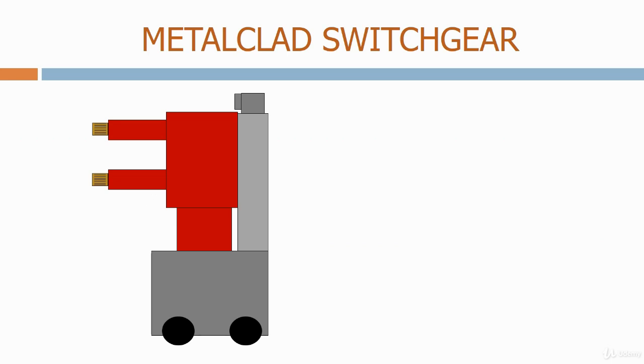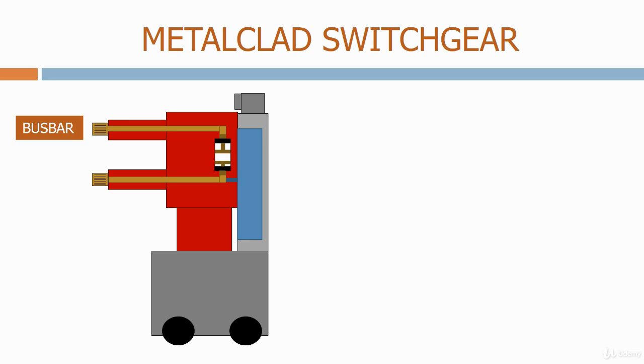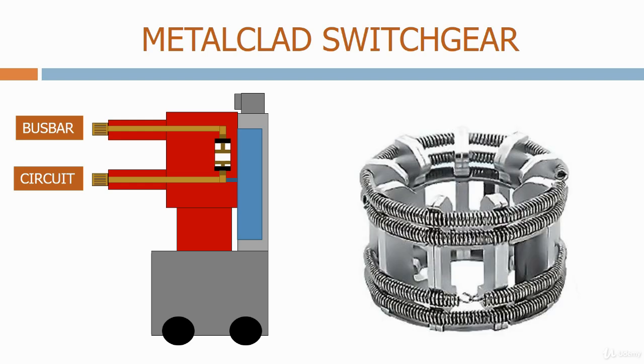Let's now look inside the truck to see what's going on. The first thing that we see is the vacuum bottle, which contains the contacts for the circuit breaker. This is connected through conductors onto contacts at the front of the circuit breaker. One of the contacts goes onto the main bus bars, and the other one connects to the individual circuit. On each of these main conductors, we have what's called a tulip contact, through which all of the current flows as it passes through the circuit breaker. These are spring-loaded and make sure that we make a good solid contact with a female connector on the main housing.